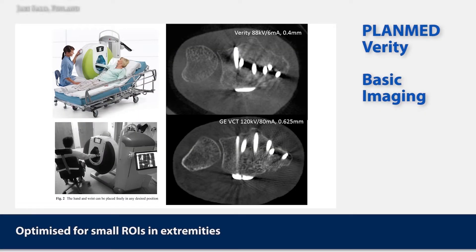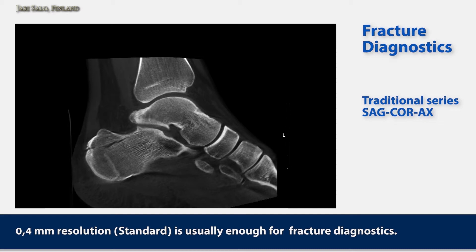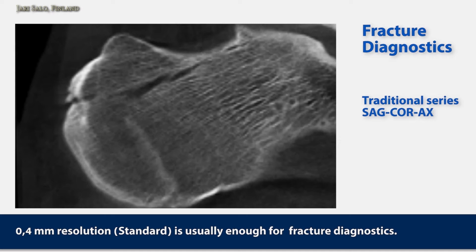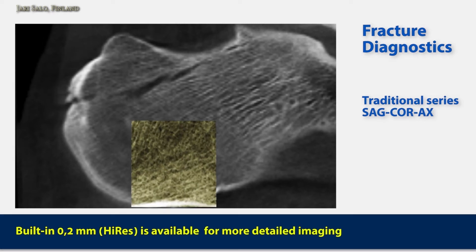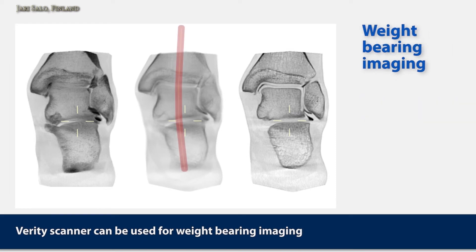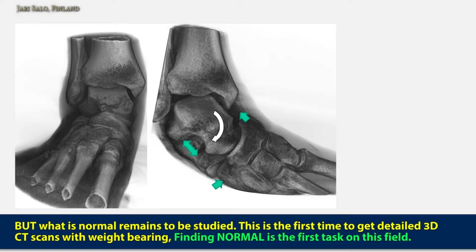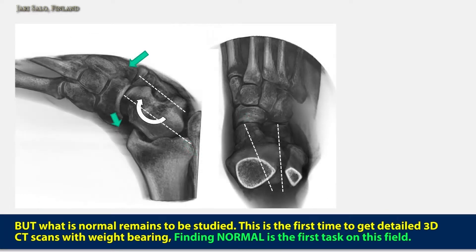The machine itself is a versatile, small machine which is ambulatory. You can have basic imaging with 0.4 millimeter resolution, which is an isotropic resolution — the same in all three directions. If you need more detailed imaging, there is a 0.2 millimeter built-in high-res option available. We can also have weight-bearing imaging — here's an example of alignment of the calcaneus and talus. We can also image special cases like a ballet dancer with an old sesamoid fracture and a painful non-union. We can stress the foot and ankle in other directions, but then we come to the problem of what is normal — for example, there is a huge movement of the Chopart area, but whether that is normal or not remains to be seen.